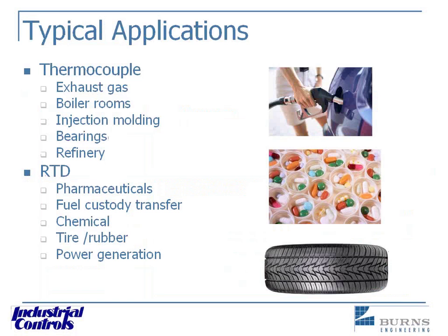Some typical applications that we run across, thermocouples, I mentioned exhaust gas on like a diesel engine, for example. And Harold, you can talk about boiler rooms for sure. And injection molding machines. Sometimes they're used a lot for bearing temperature, although RTDs are used there also. And then some of the oil refinery temperature points are beyond what an RTD can handle, so they're used very commonly there.